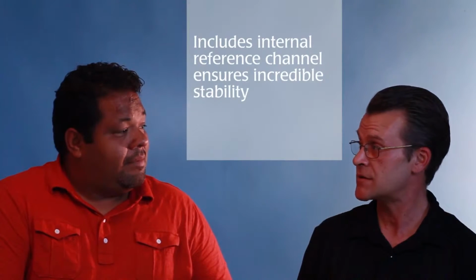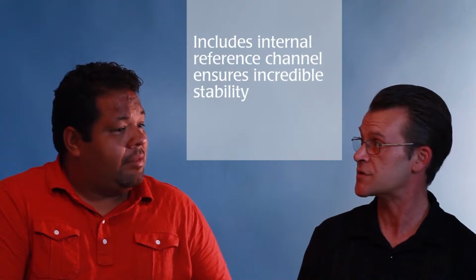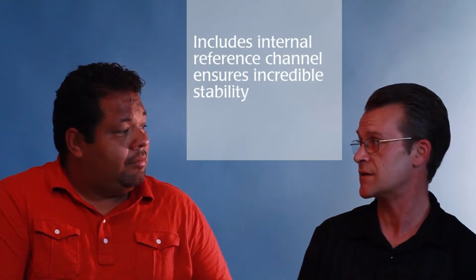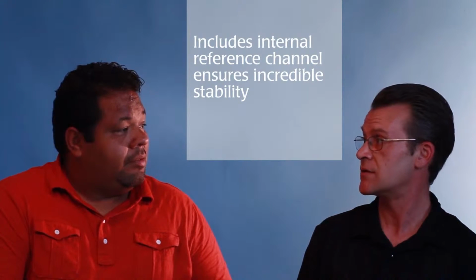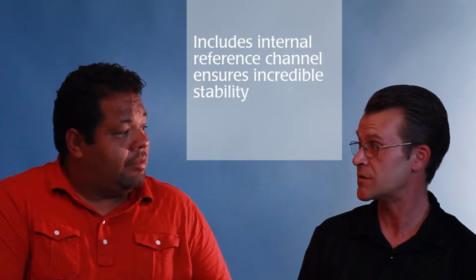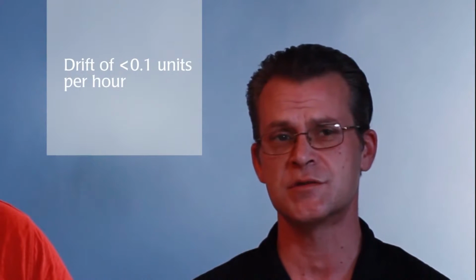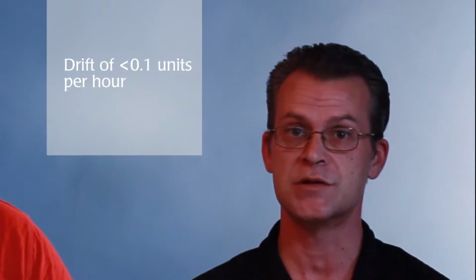We thought about this, and we actually took a novel approach: an internal reference channel inside the instrument that's going to counteract the effects of these temperature or current changes. This results in a very, very stable instrument, which has a drift stability of less than 0.1 units per hour.